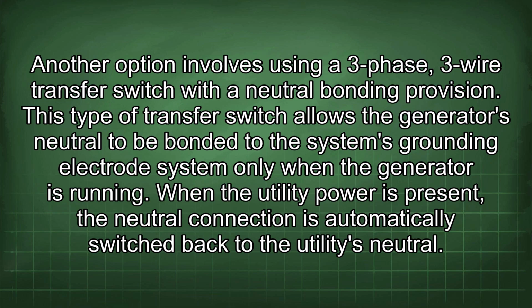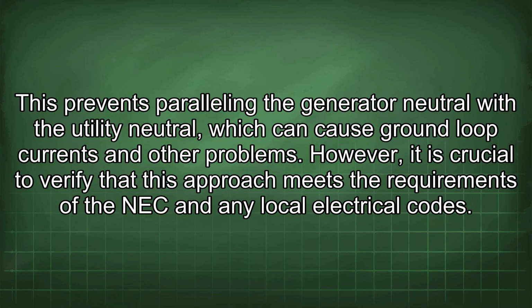This type of transfer switch allows the generator's neutral to be bonded to the system's grounding electrode system only when the generator is running. When the utility power is present, the neutral connection is automatically switched back to the utility's neutral. This prevents paralleling the generator neutral with the utility neutral, which can cause ground loop currents and other problems. However, it is crucial to verify that this approach meets the requirements of the NEC and any local electrical codes.